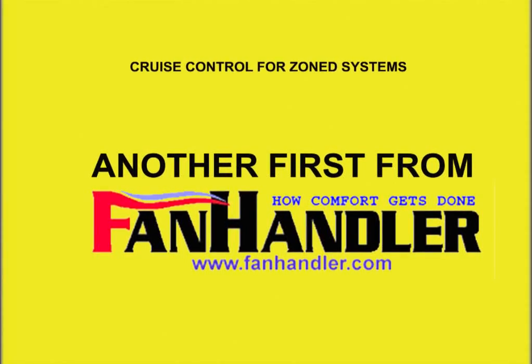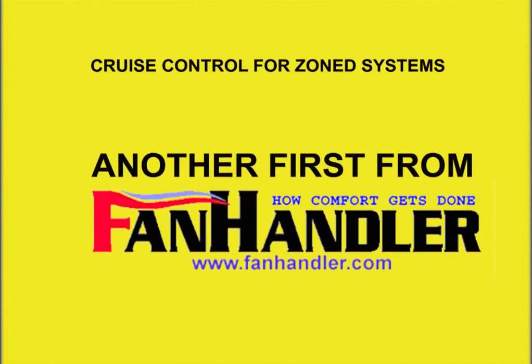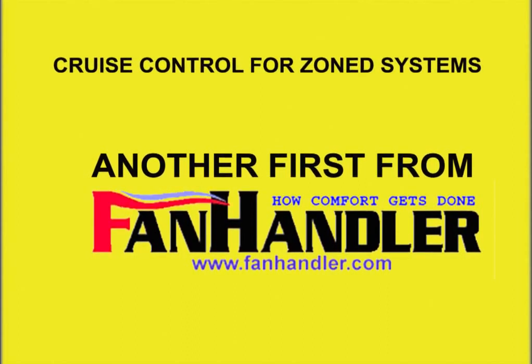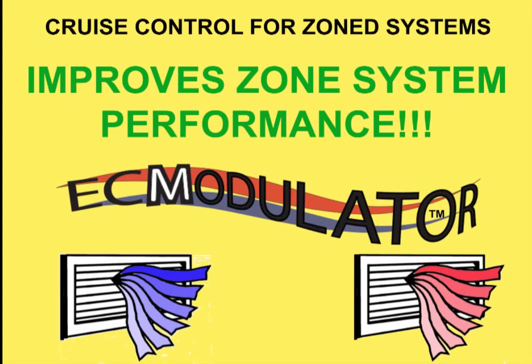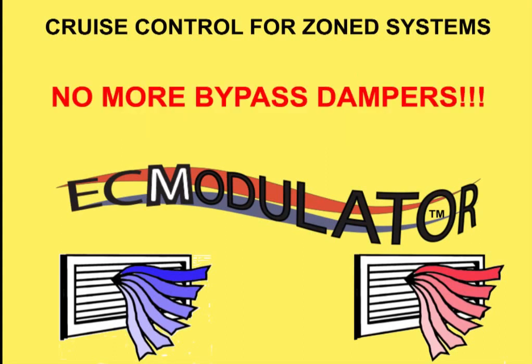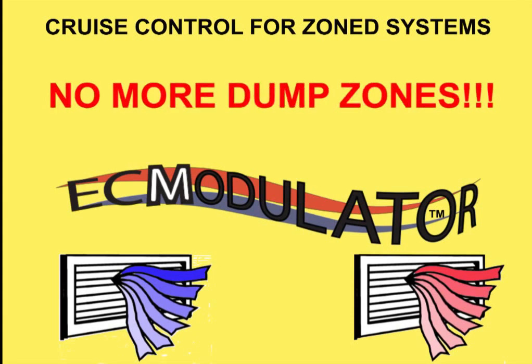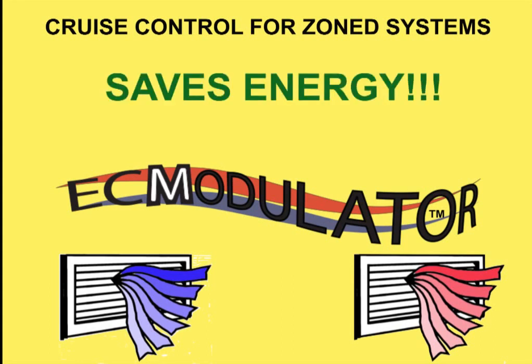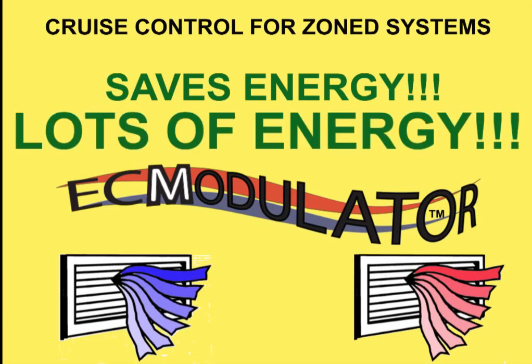This short video will demonstrate the ability of the ECM modulator to regulate the speed of an HVAC blower in response to delivered air temperatures. In addition, for zone systems, the ability to modulate up to but not surpass a precisely controlled and easily field adjustable duct pressure setting.